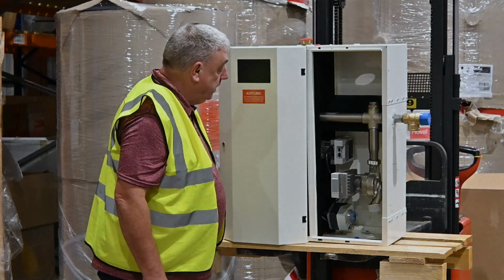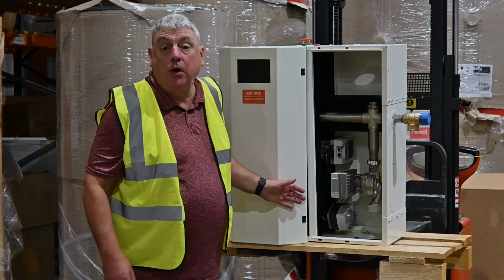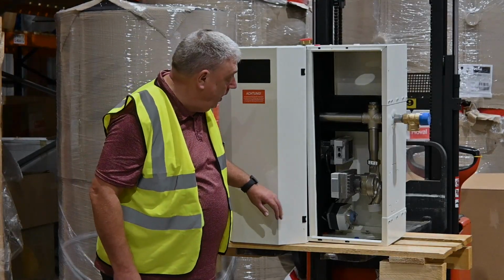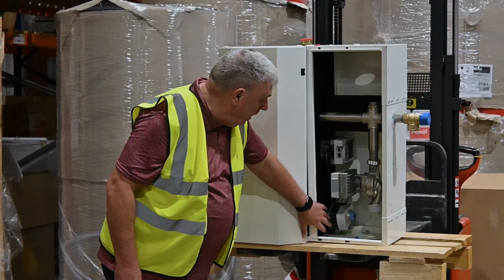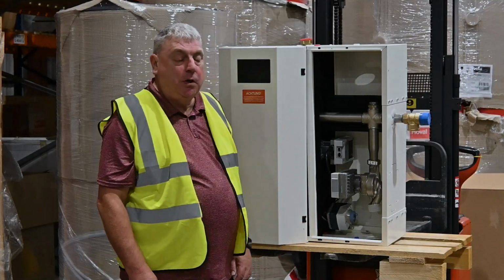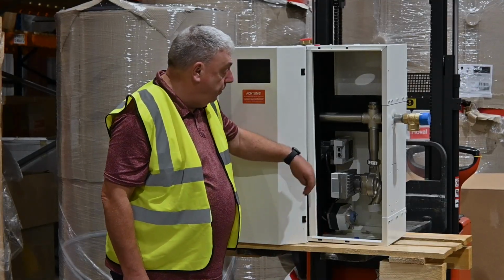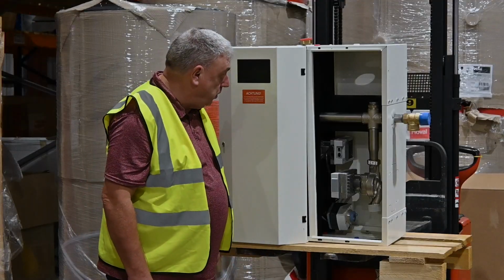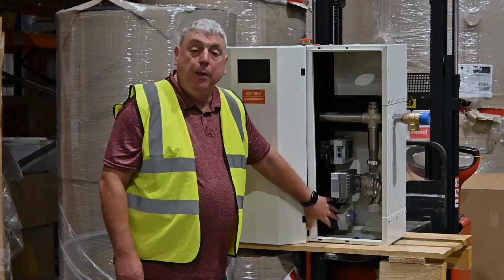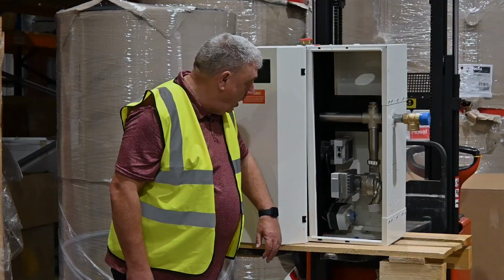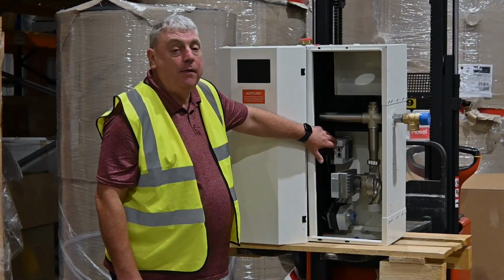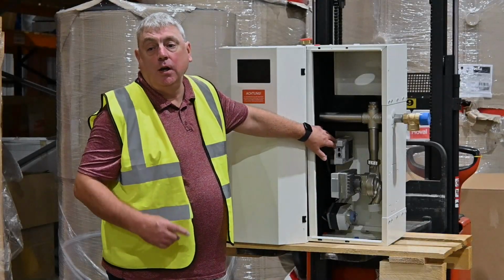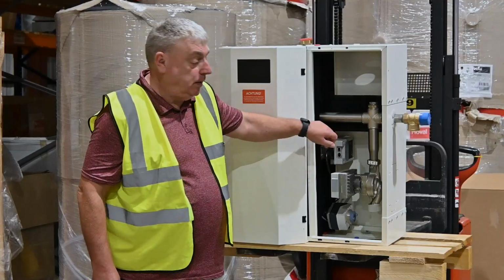Across the other side of the heat exchanger, the heating supply and return, the bit we've talked about already, we've got initially that would enter through the bottom, and go back to the heat generator from the bottom as well. And we have a 3-port valve, a mixing valve, which is motorised, and then a high efficiency pump to have that circulation around the primary side of the heat exchanger.